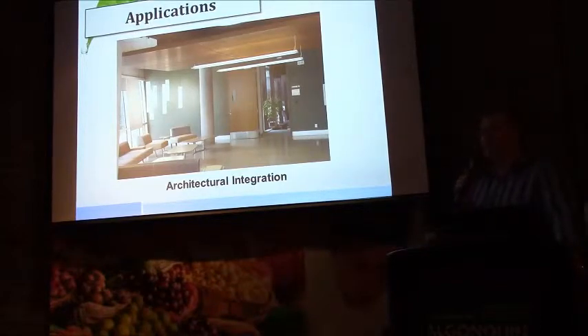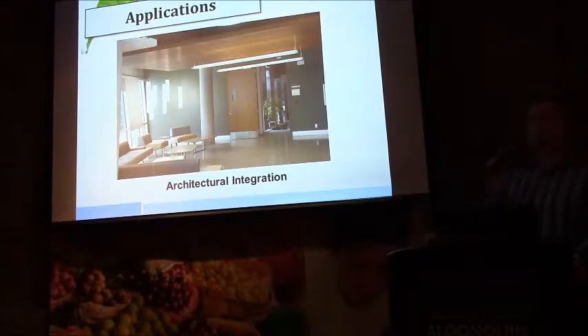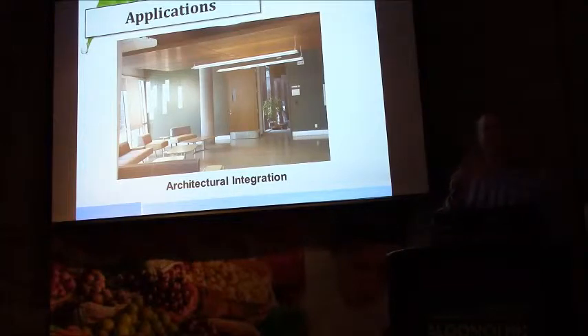And so for free hung beams, a coanda wing or some extension is a necessary evil. And generally that adds overall roughly about a foot of width to the active beam. So in this application, that beam would be 3 feet wide and mounted about 12 inches from the backside of that open wooden slat ceiling. And then the discharge path becomes important as well, relative to ducts not being mounted in the way and creating a downdraft current into the room.